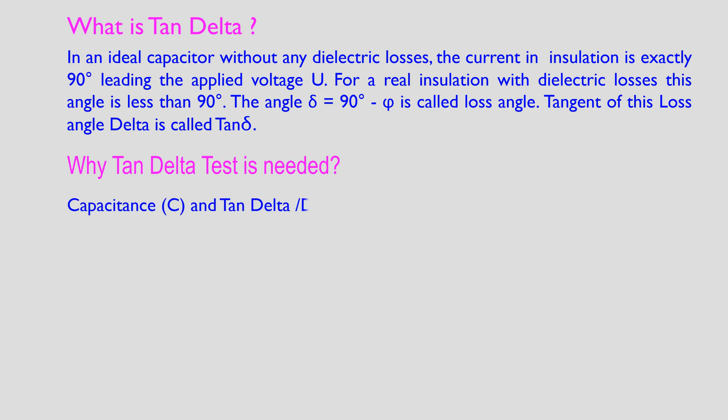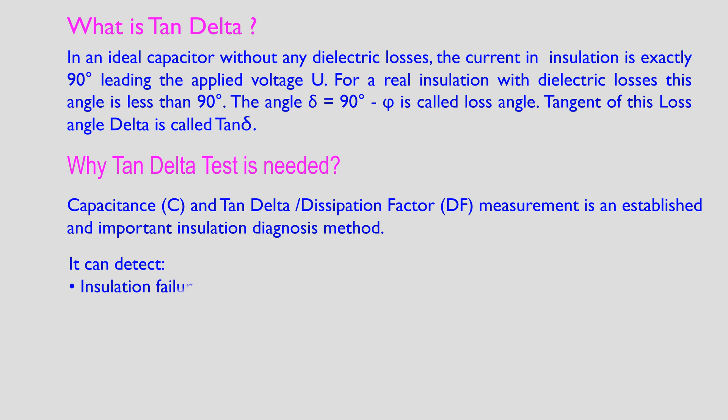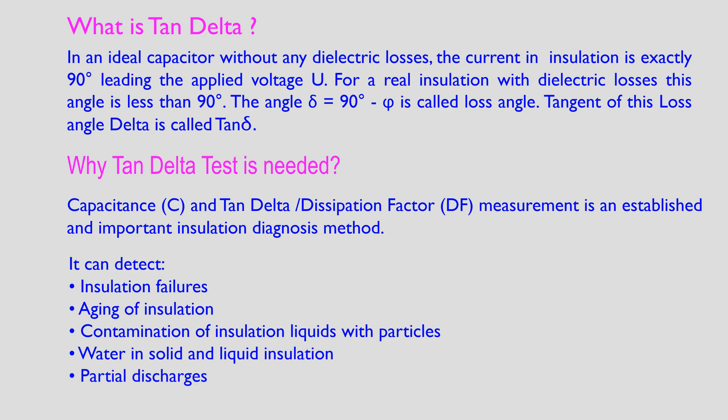Capacitance C and tan delta, also called dissipation factor DF measurement, is an established and important diagnosis method. It can detect insulation failures, aging of insulation, contamination of insulation liquids with particles, water in solid and liquid insulation, and partial discharges.